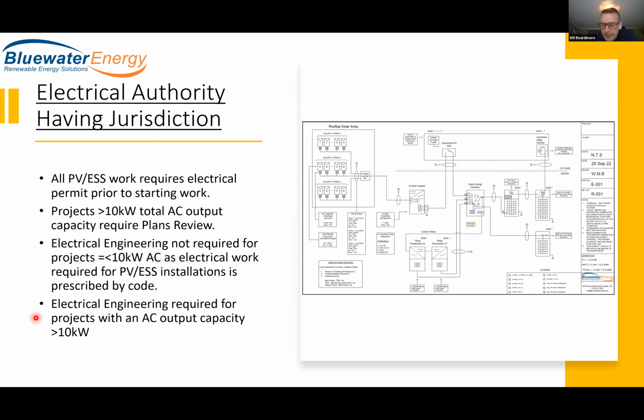The electrical authority having jurisdiction in Ontario is the Electrical Safety Authority. Other provinces have their own electrical authority and inspectors. All provinces base their code, if they don't have an individual one, on the Canadian Electrical Code. So the requirements are pretty standard here. All PV and electrical or energy storage systems require permitting prior to starting work. Projects greater than 10 kilowatts total AC output capacity, which includes the PV inverter and any AC output from your energy storage systems, such as a Tesla Powerwall. A Tesla Powerwall is a 5 kilowatt generator in terms of output capacity, and that's how the utility and the electrical authority view it. So a 10 kilowatt PV system with one Powerwall puts us at 15 kilowatts of total generation, and we require plans review. So that's how that works.